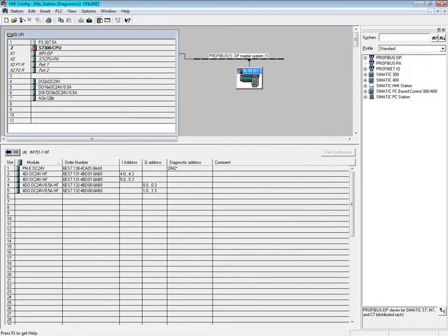It was found that one of the incoming power wires was not solidly connected. The wire was seated properly and the terminal retightened, which fixed the problem. To refresh the online hardware configuration, press the F5 key. The station is now up and running, and that concludes this video.